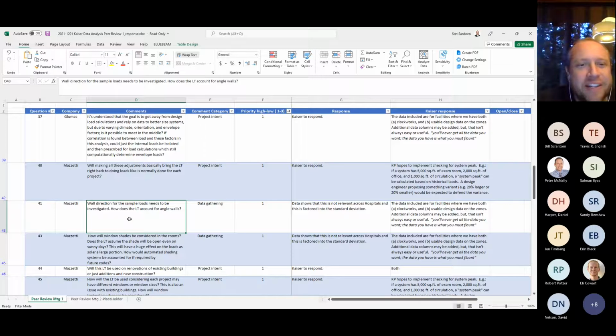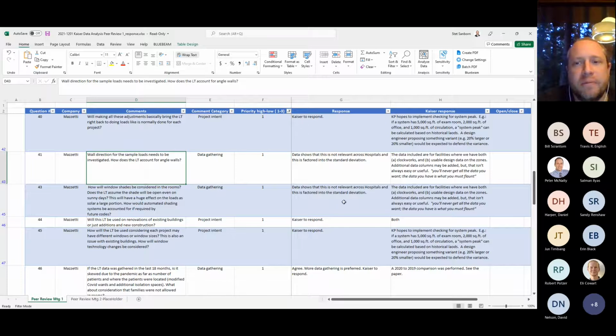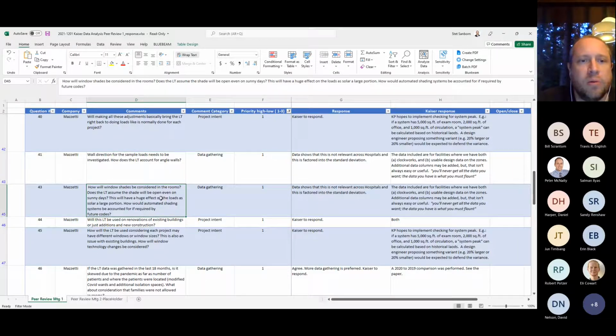The next couple of items again look at that variability of orientation or some of the elements within the room. As designs change, expectations on the system side may need to be adapted. I think the key thing we're coming away with is that the actual peak room loads we're calculating aren't that far off. Whether you're looking at different wall orientations, or in 43, some forms of automated shading or more aggressive facade controls, at the end of the day those room loads are still pretty close to what we've actually measured in the field compared to the design loads. So I don't think there'd be a big change there, but we'd still challenge the team to look at what the diversified loads are.